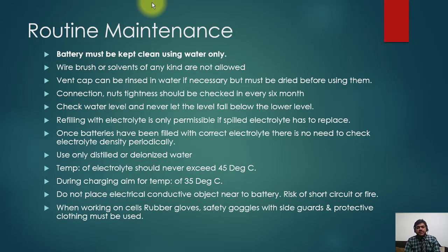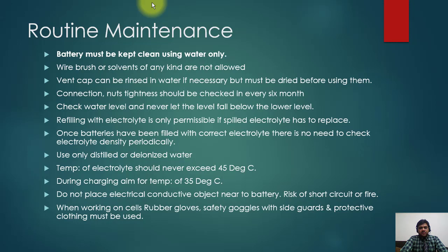Connection nut tightness should be checked every six months. Check the water level and never let it fall below the lower level mark — if the level falls below that point, the battery plates will be exposed to air and will be damaged very quickly. Refilling with electrolyte is only permissible if spilled electrolyte needs to be replaced. Normally, if the electrolyte level is low, you simply refill with distilled water. If you keep adding electrolyte, the specific gravity will rise, which is not recommended by the manufacturer. Once batteries have been filled with the correct electrolyte, there is no need to check electrolyte density periodically.